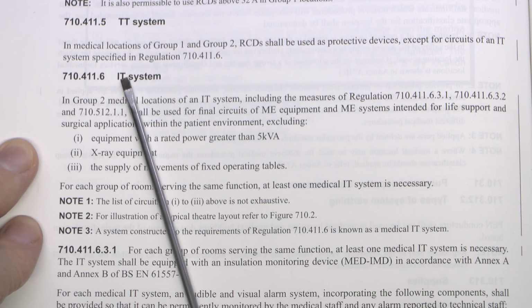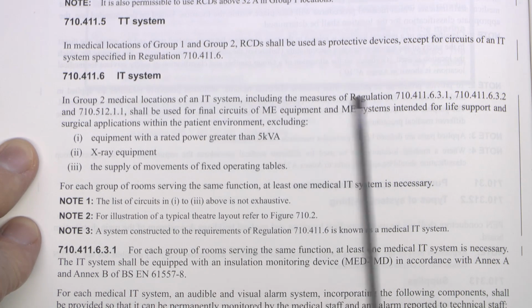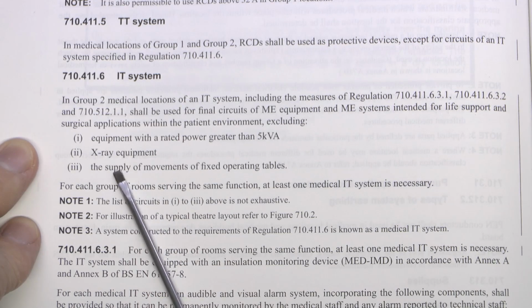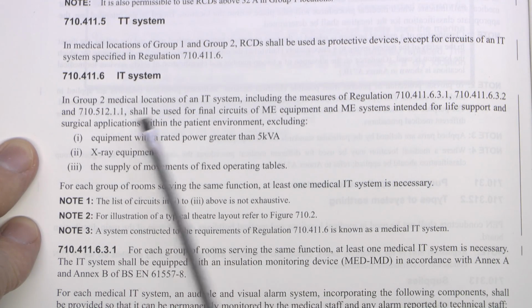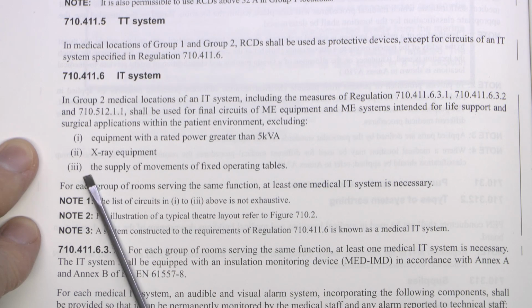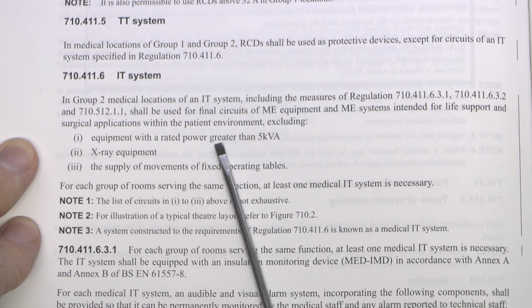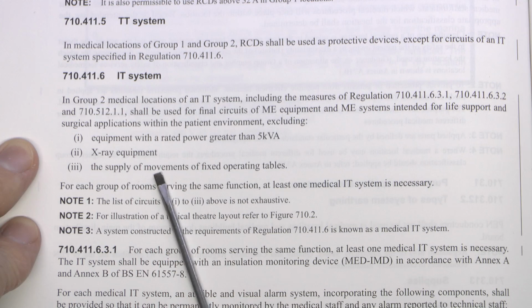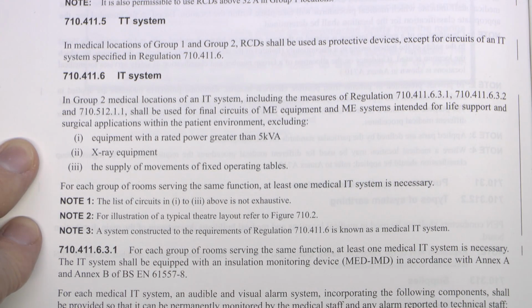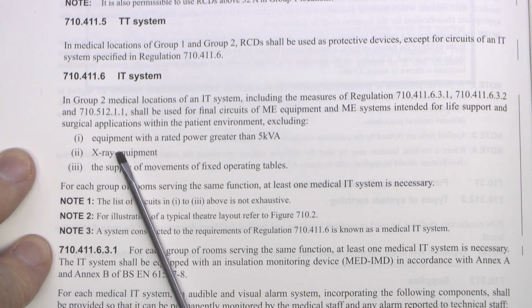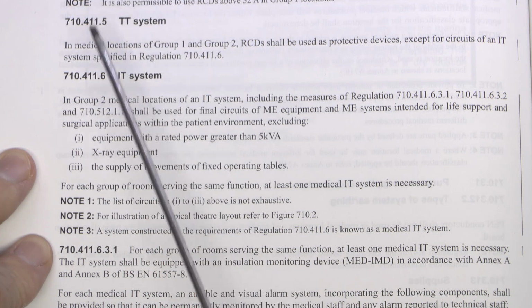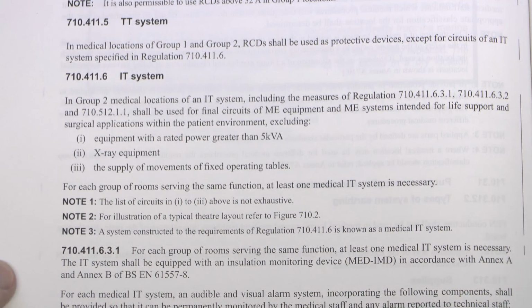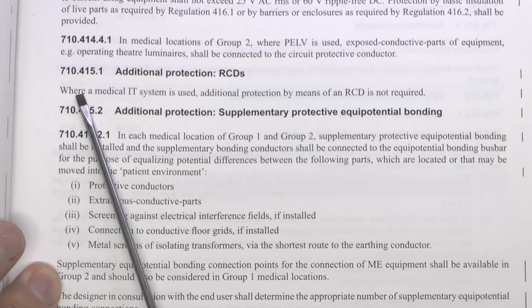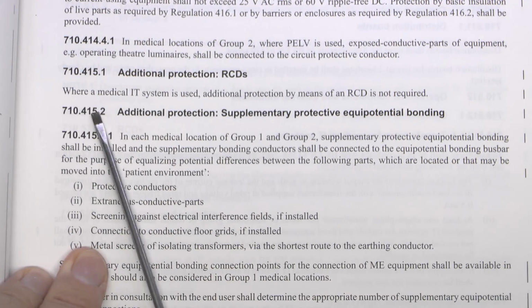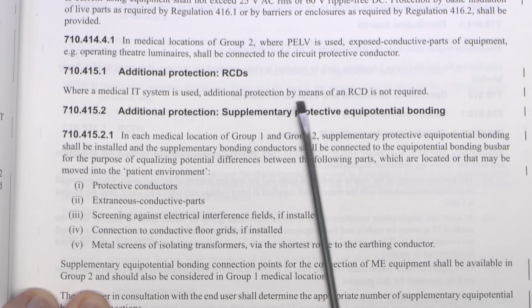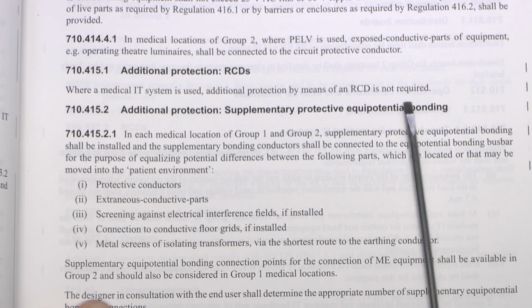710.411.6, the IT system. And what's happened here is, again, it's basically the same content, but we've actually got a list of various types of equipment here. So rather than just having a general list there, it's been put into these 3 called out points: equipment with the rated power greater than 5 kVA, X-ray equipment, and the supply movements of fixed operating tables. Some of that was actually previously in the 710.414 that we saw up there, so it gets a bit of a rearrangement and alteration there. Now 710.415.1 is a new one, and it's where a medical IT system is used. Additional protection by means of an RCD is not required.